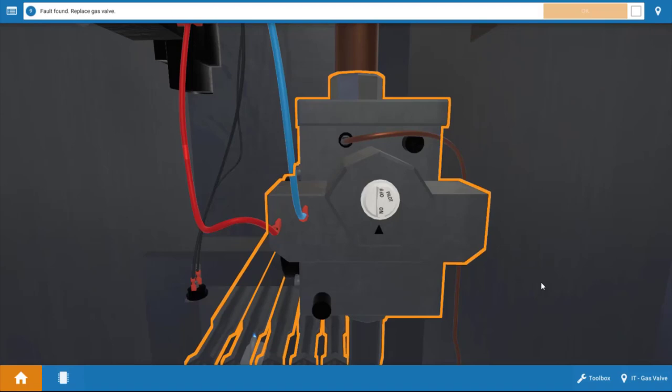Another suggestion would be to measure the main gas pressure coming into the gas valve. If it's unusually low, that may result in the gas valve not opening as well. But in this case, it's an electrical problem.